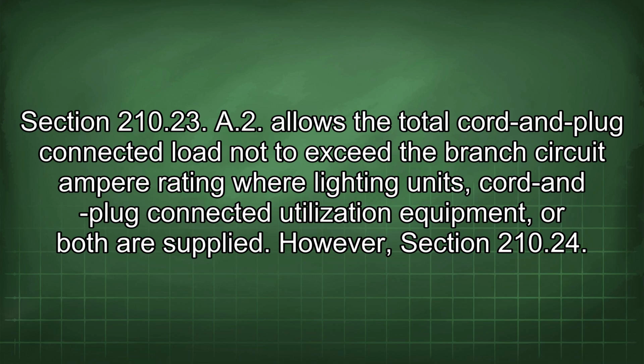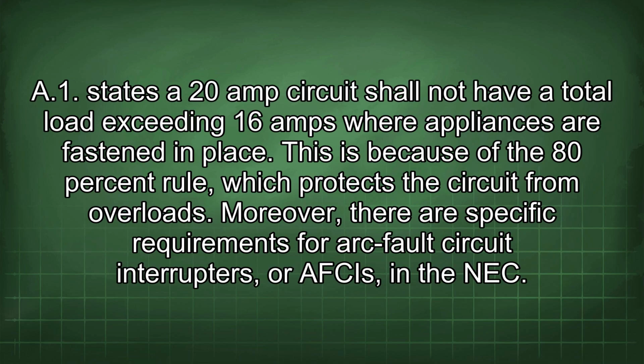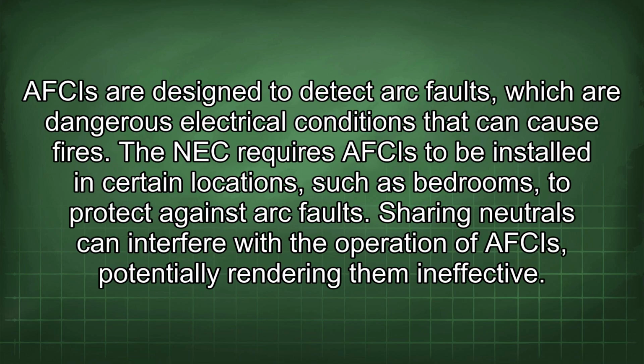However, Section 210.24 A1 states a 20 amp circuit shall not have a total load exceeding 16 amps where appliances are fastened in place. This is because of the 80% rule, which protects the circuit from overloads. Moreover, there are specific requirements for arc fault circuit interrupters, or AFCIs, in the NEC. AFCIs are designed to detect arc faults, which are dangerous electrical conditions that can cause fires. The NEC requires AFCIs to be installed in certain locations, such as bedrooms, to protect against arc faults.